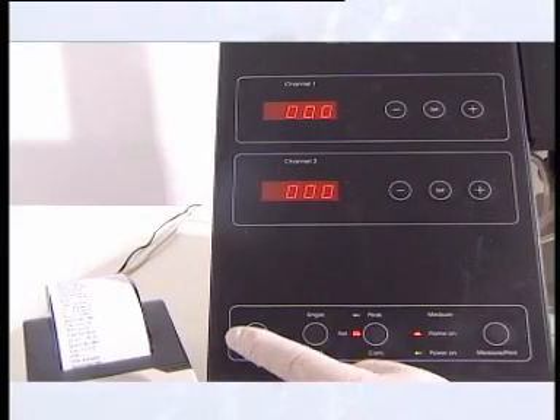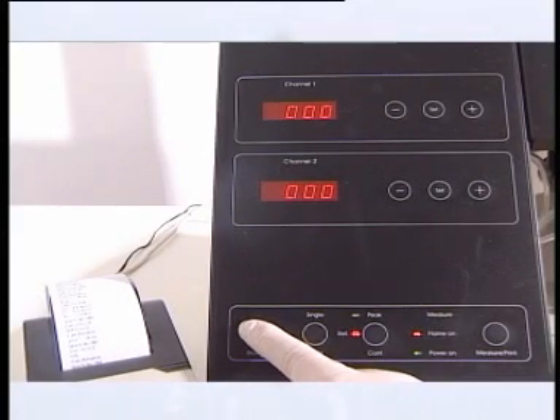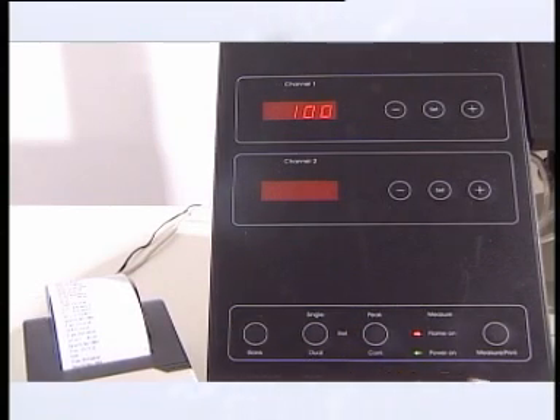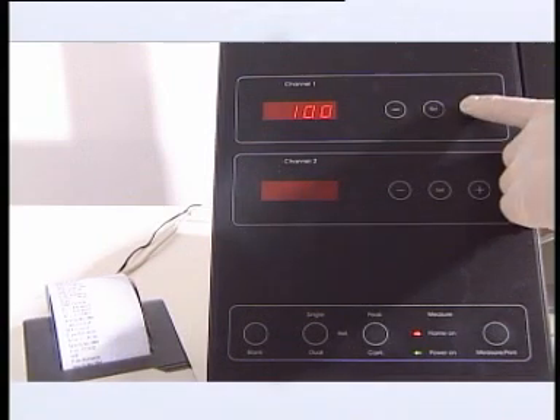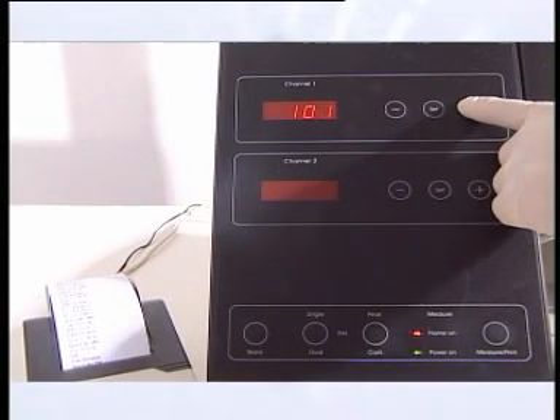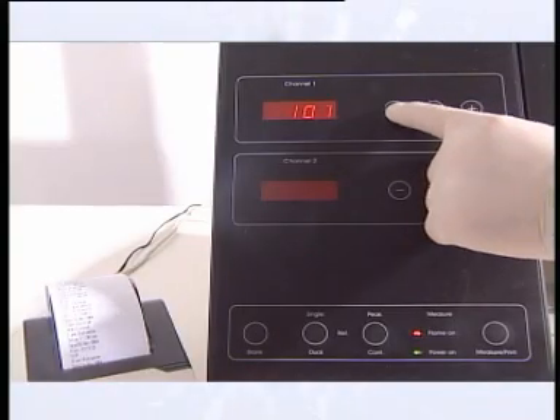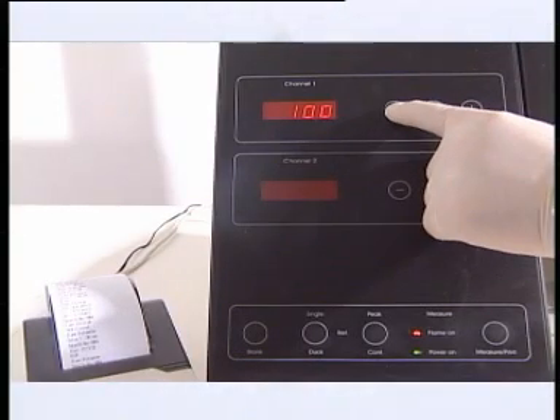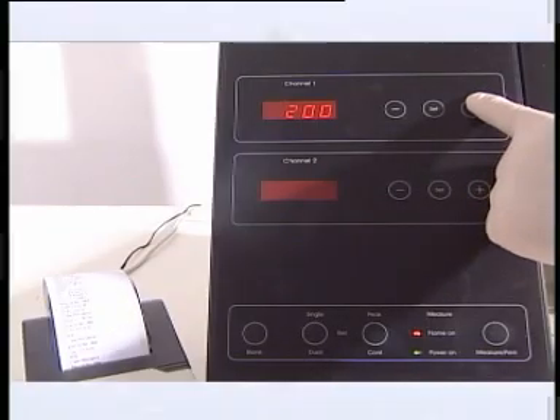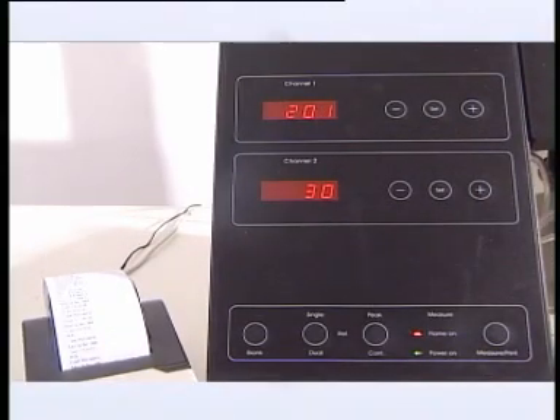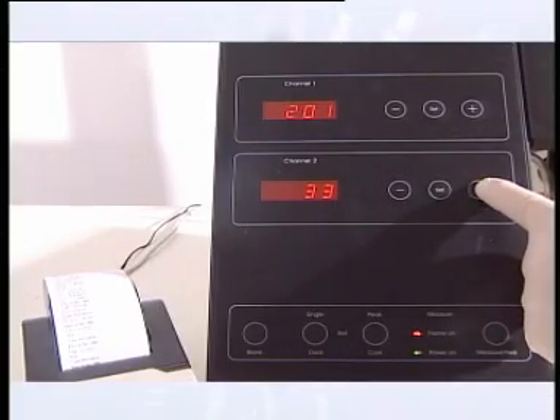If the blank is held for a longer time, the third function is seen. First, 100 appears. This sets the instrument into clinical mode 101 or industrial 100. The 101 mode will print out the values in millimoles per litre. Set is pressed and 200 is seen. This is where a delay can be installed to allow a longer time before the stable reading is taken in calibration and measurement.